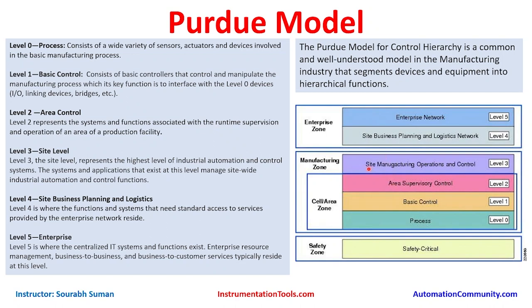Level 3 is site manufacturing operations and controls — the highest level of industrial automation and control systems. The systems and applications at this level manage site-wide industrial automation and control functions. Workstations, HMIs, operator workstations, and engineering workstations reside here, from where commands and logic are built and downloaded. This is essentially the control room or engineering room of a plant, hosting all DCS software solutions such as Tristation, Foxboro, Emerson DeltaV, Honeywell, Yokogawa, or Siemens DCS.